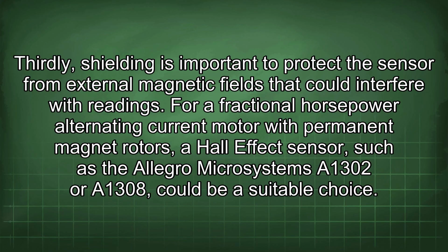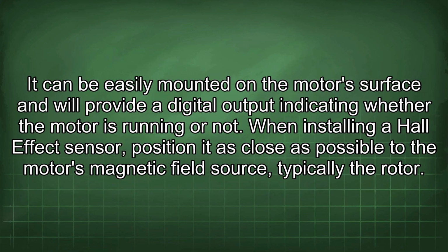For a fractional horsepower alternating current motor with permanent magnet rotors, a Hall effect sensor such as the Allegro Microsystems A1302 or A1308 could be a suitable choice. It can be easily mounted on the motor surface and will provide a digital output indicating whether the motor is running or not.